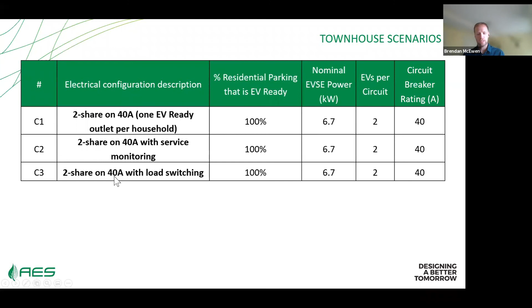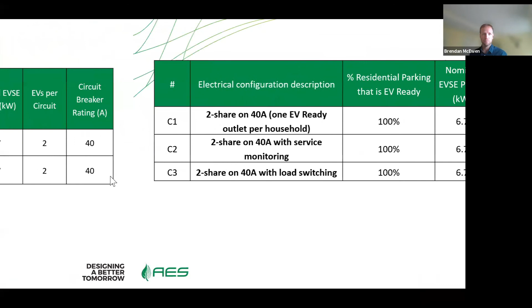We also looked at it with load switching, where you'd have control on a branch circuit and could charge your vehicle or run your dryer, but not both. This avoided upgrading a panel from 100 amps to the next larger size increment because of the additional 40 amps for charging - it could be accommodated within the load calculation for the whole building.